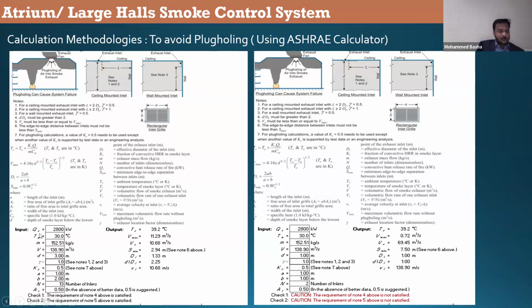QC, you need to use the QC value here. This is why I was explaining what QC is. You need to understand this is the convective heat release rate, which is 70% of the Q. Here you will not use Q directly, because this is not dealing with the fire directly, whereas it deals with the convective heat of the fire, which is away from the fire. So 2800 kilowatt, I am using the outside air temperature of 30 degrees Celsius.